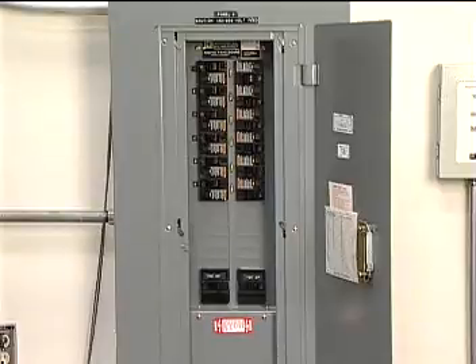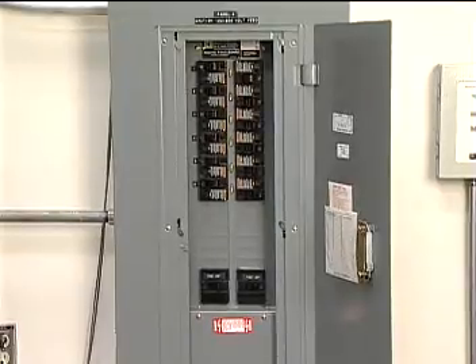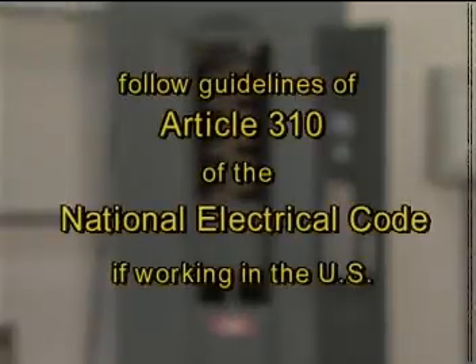Raychem, approval agencies, and national electrical codes all require the use of ground fault protection of equipment for electric heat tracing installations. Also be sure to follow the guidelines of Article 310 of the National Electrical Code if working in the U.S. for branch circuit wiring. There are many types of ground fault protection devices, so be sure to follow the manufacturer's recommended installation procedures.